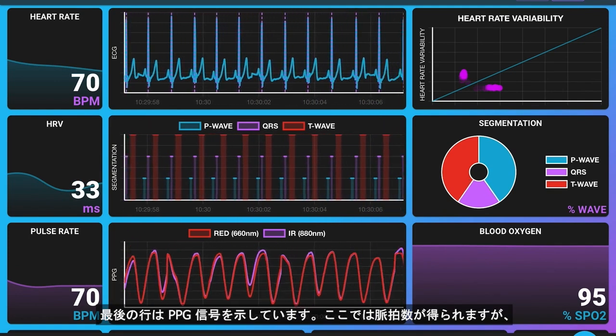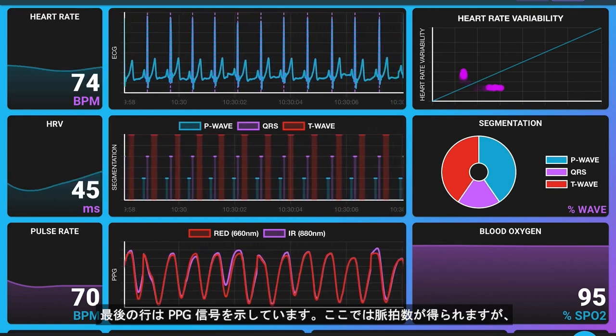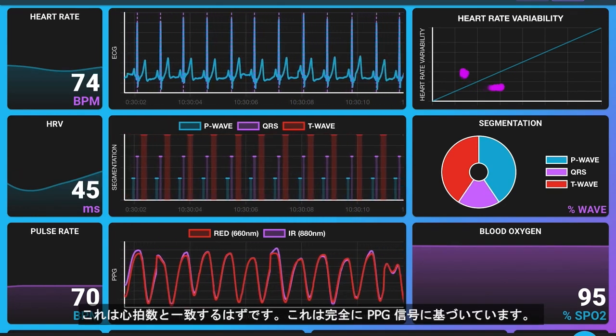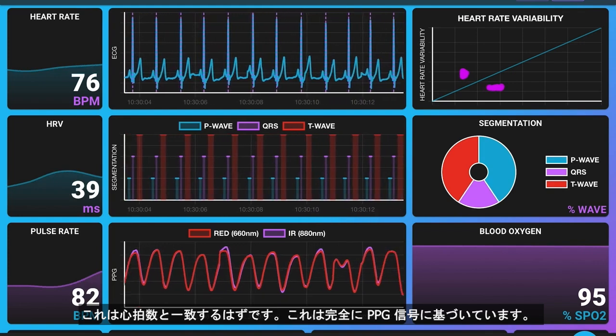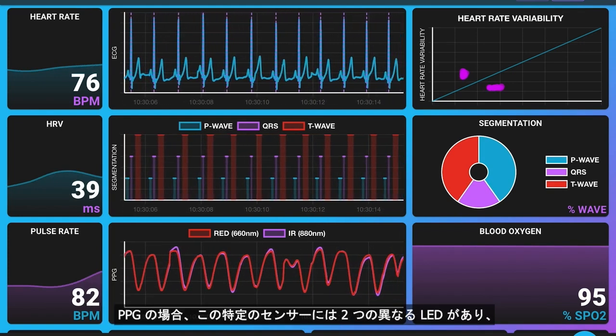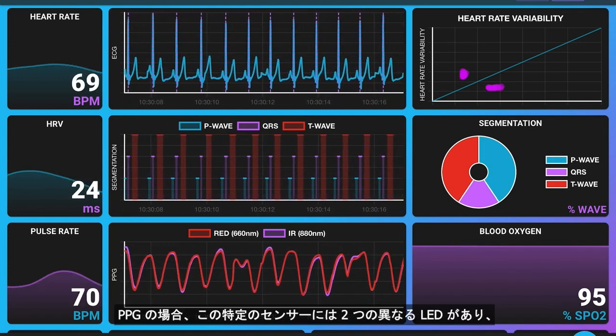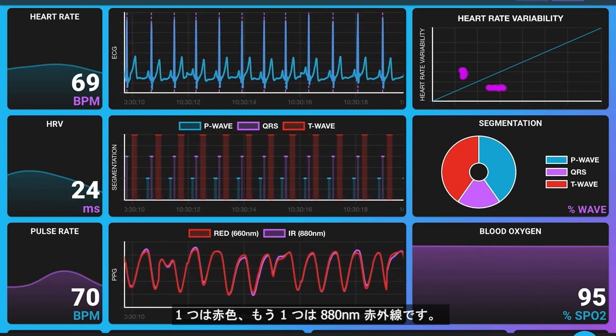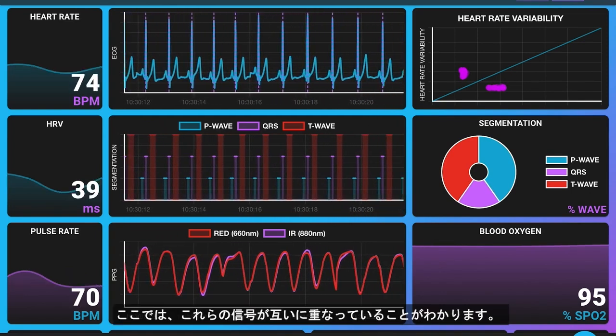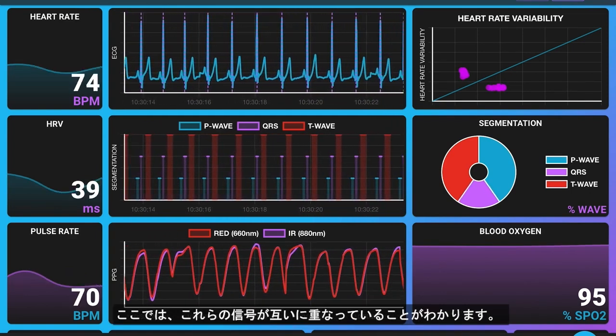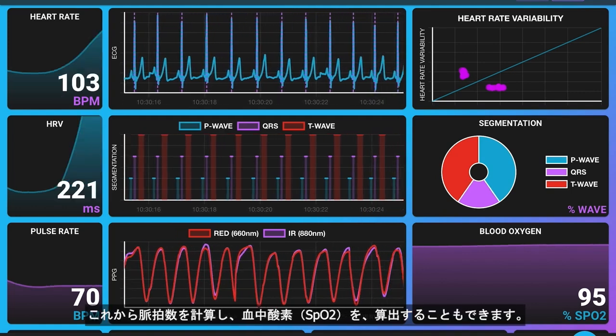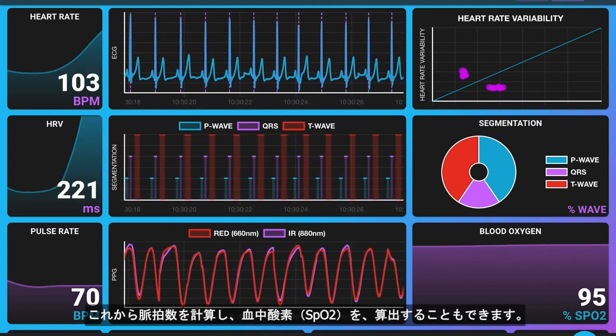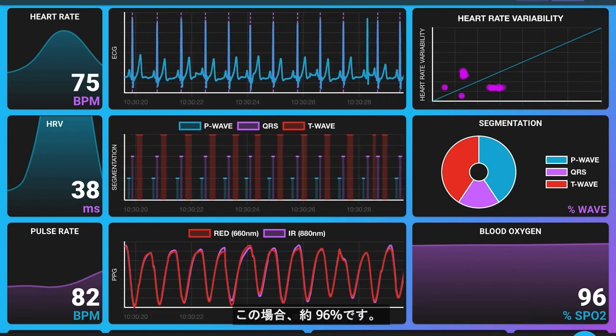The last row is showing you the PPG signal. Here we're getting the pulse rate, which should coincide with the heart rate — this is based purely off of the PPG signal. This particular sensor has two different LEDs: a red one and an infrared at 880 nanometers. We can see that those signals overlap each other. From this, we're calculating the pulse rate, and we're also able to derive the blood oxygen — the SpO2 — around 96.